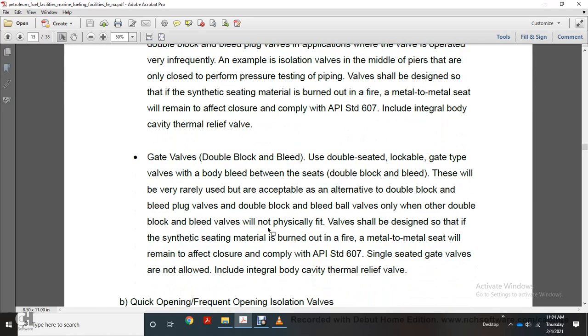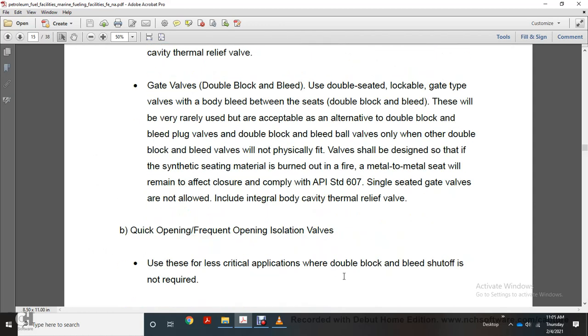Gate valves, double block and bleed: double seated, lockable gate type valve with a body bleed between the seats of the double block and bleed. These will very rarely be used, only when the acceptable alternatives, double block and bleed plug valves or double block and bleed ball valves, will not physically fit. The valve should be designed so that the synthetic seating material is burned out in a fire, and metal to metal seats will remain effective for closure. Comply with API standard 607. Single seated gate valves are not allowed. Include an integral body cavity thermal relief valve.